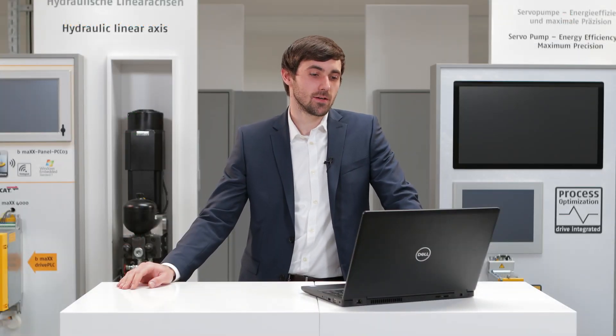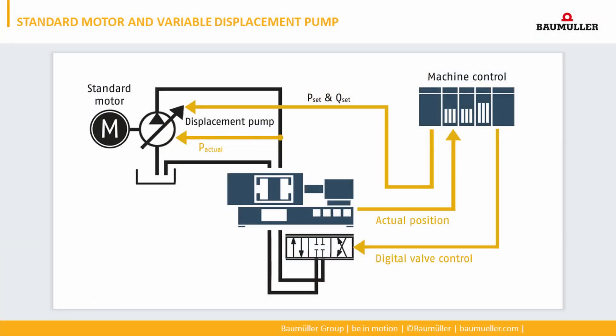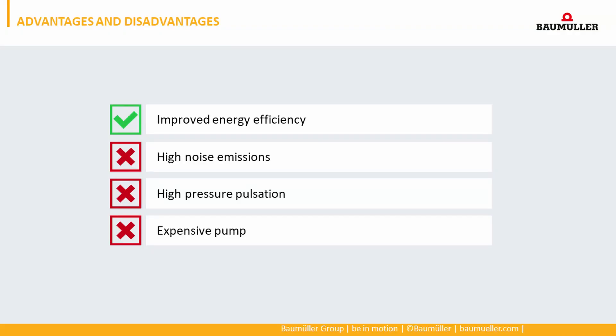The next system is a combination of a standard induction motor with a variable displacement pump, typically a piston pump. The motor speed is constant here too, but a big difference is the variable displacement pump. The pressure and flow command goes directly to the pump, and by changing the displacement volume, pressure and volume control is realized. Position control and valve switching is done by the overlaid machine control. Here we have improved energy consumption, but there are still disadvantages: high noise emission, high pressure pulsation and an expensive pump.